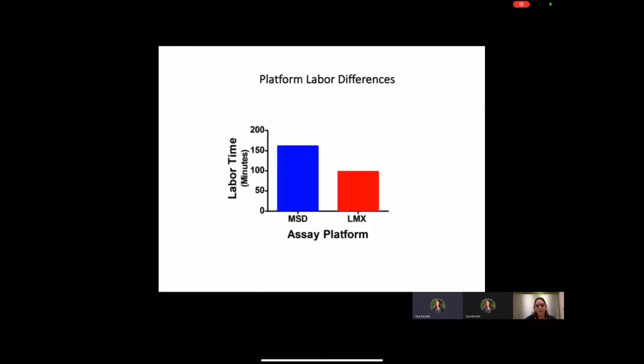Our time-in-motion study revealed that more labor is required for the MSD platform, here shown in blue. The MSD platform had increased hands-on labor time, which really reflects the time needed to prepare three plates and three separate standards, which is roughly an extra hour.